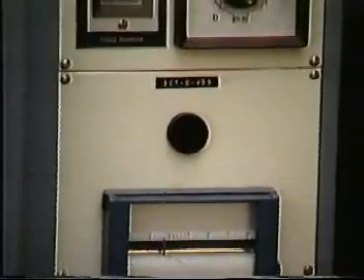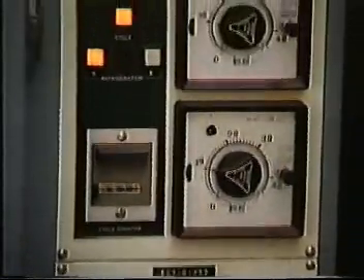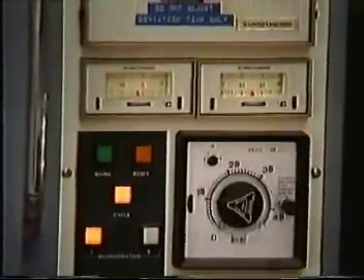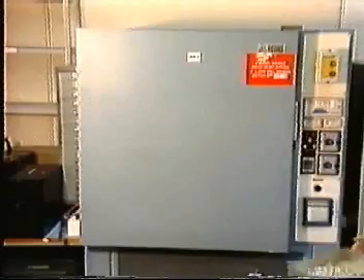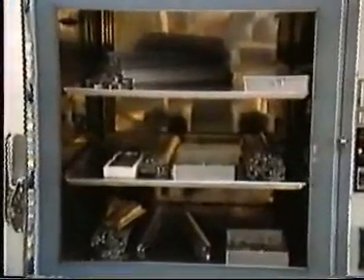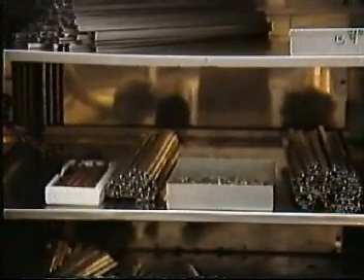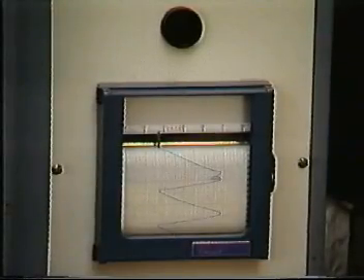At this early stage, we very deliberately seek early life failure of a component, or any change to the specified parameters provided to our suppliers. These components, for example, have just been subjected to a cycle of 10 thermal shocks at a temperature variance ranging from -5 degrees centigrade to +70 degrees centigrade at a rate of change of 1 degree centigrade per minute.